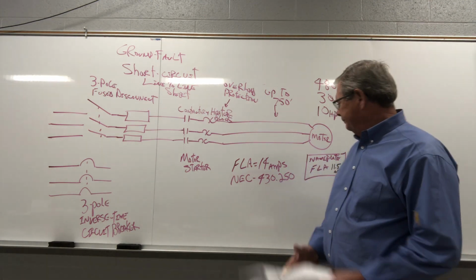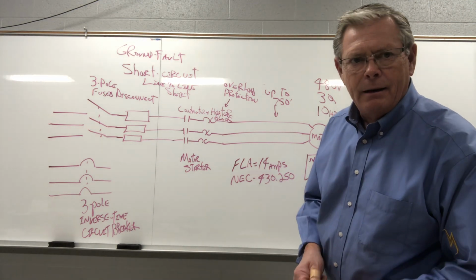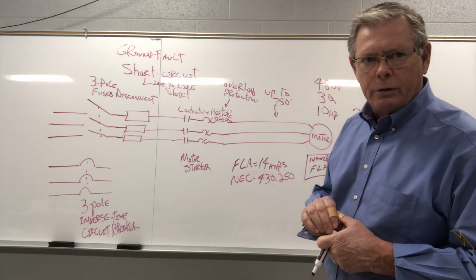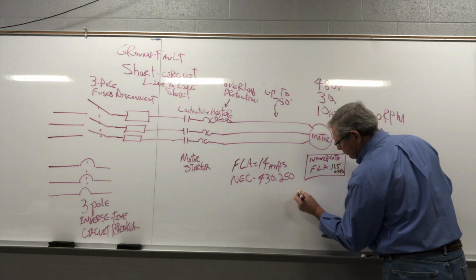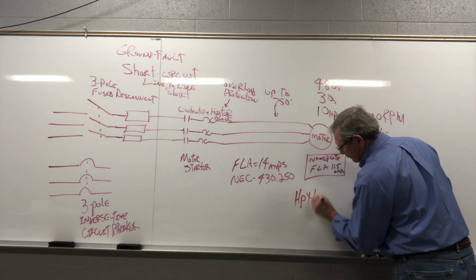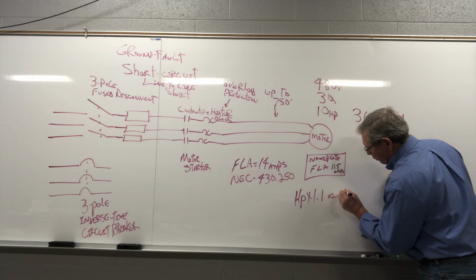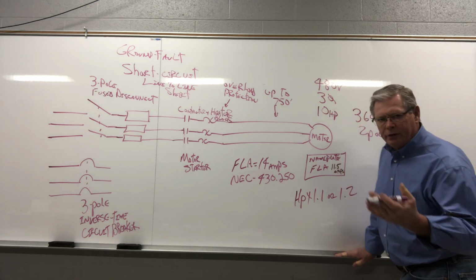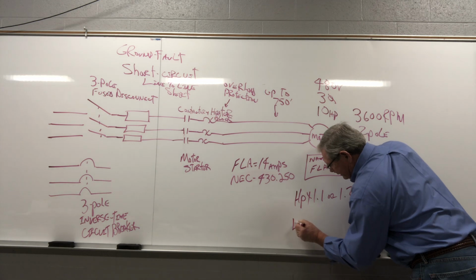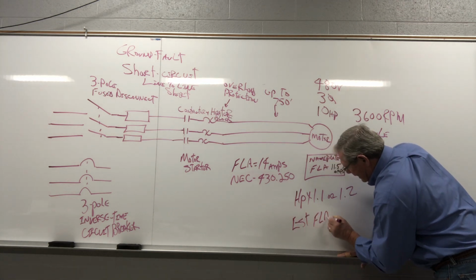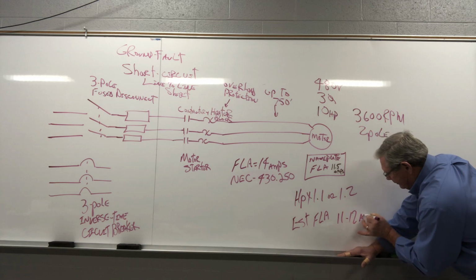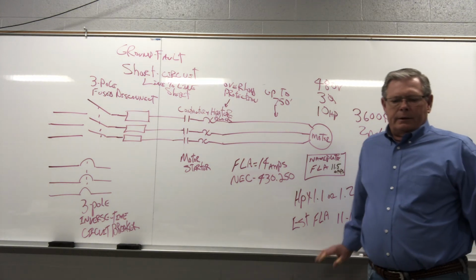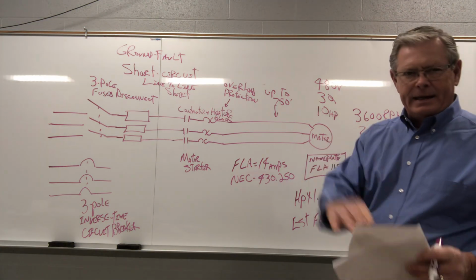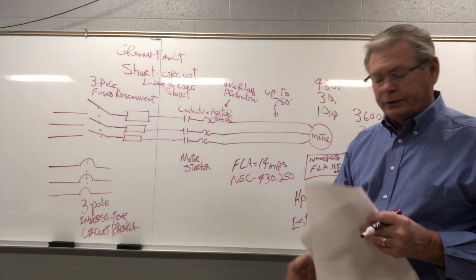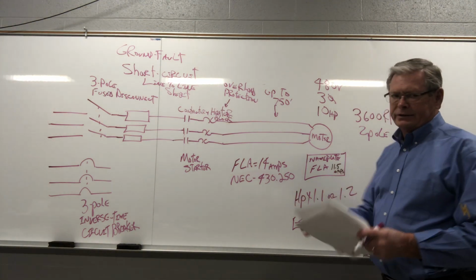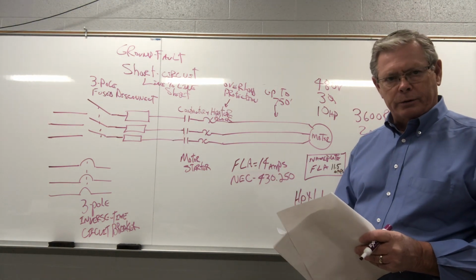But if you remember how to guesstimate a 480 volt motor full load current, okay? If you take horsepower times 1.1 or 1.2, that will give you a good estimate of FLA. That's an estimate of FLA of 11 to 12 amps. Now, that's just a guesstimate if you can't get to a nameplate to help you troubleshoot, all right? But the nameplate on this is 11.5 amps, and let's say it's a GE motor.